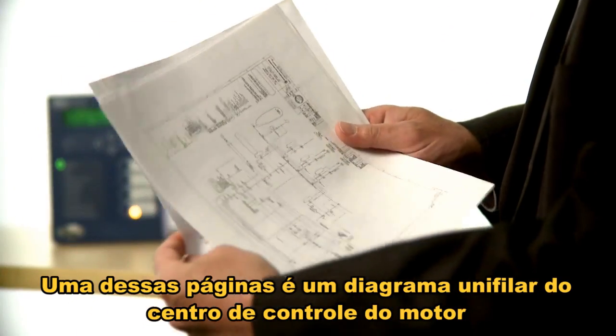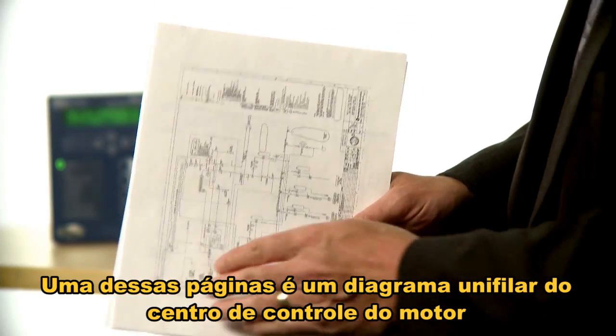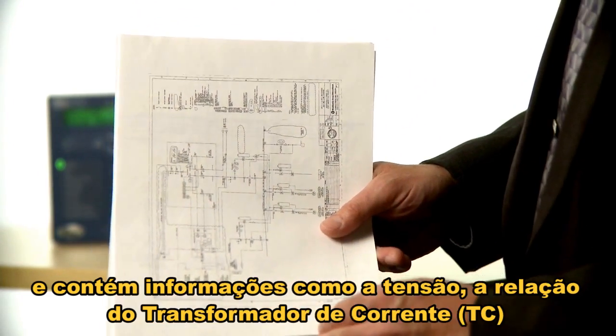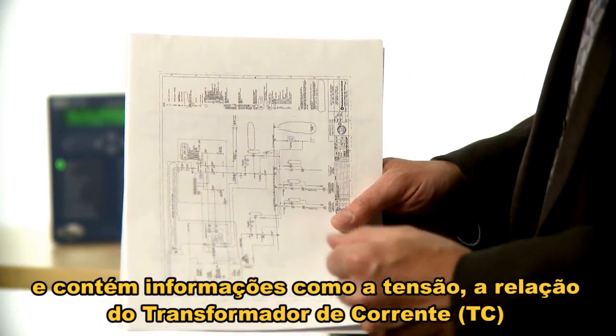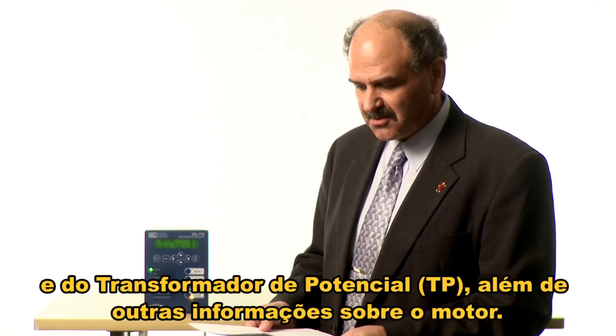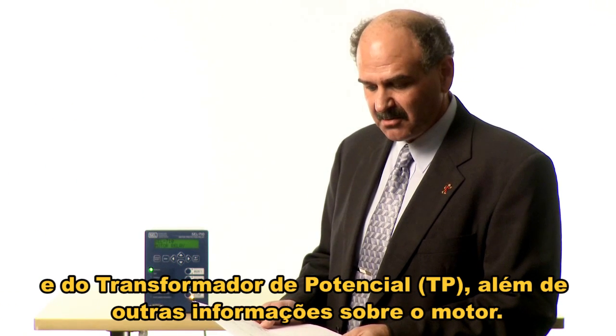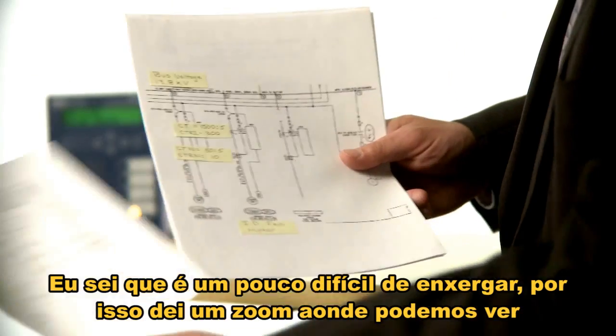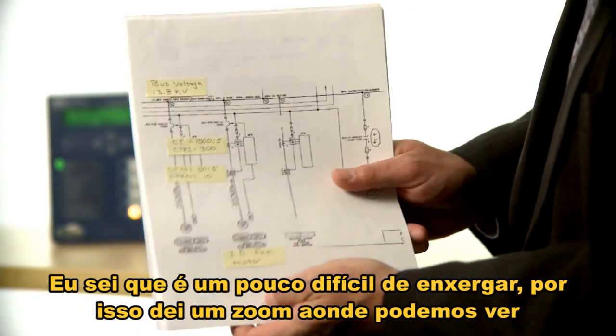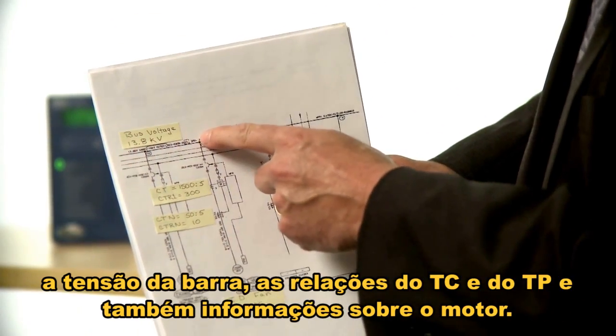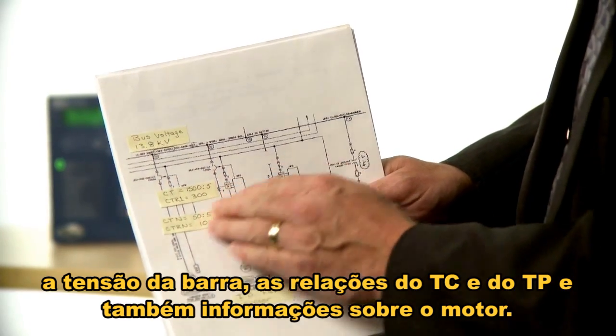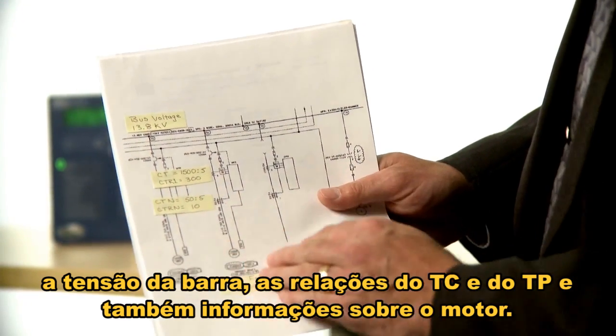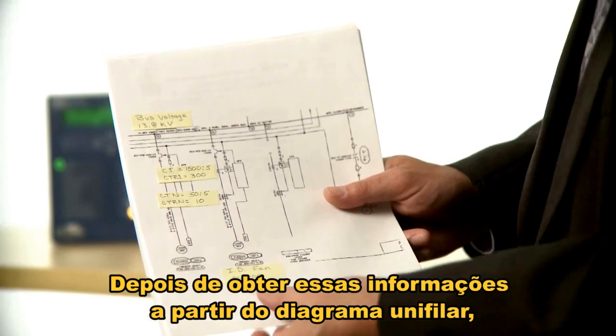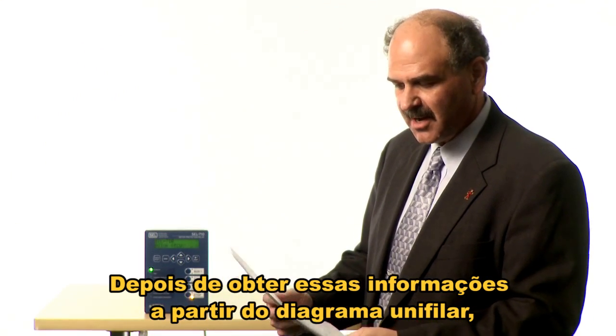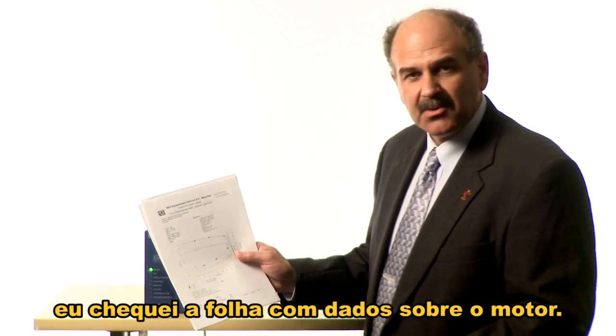Now, one of those sheets is a motor control center one-line diagram, and it contains information such as the voltage, the current transformer and the potential transformer ratios, as well as some other motor information. I know it's a little hard to see, so I did a little zoom in where you can go in and see the bus voltage, pull out the CT ratios, pull out the PT ratio, and have the motor information as well.